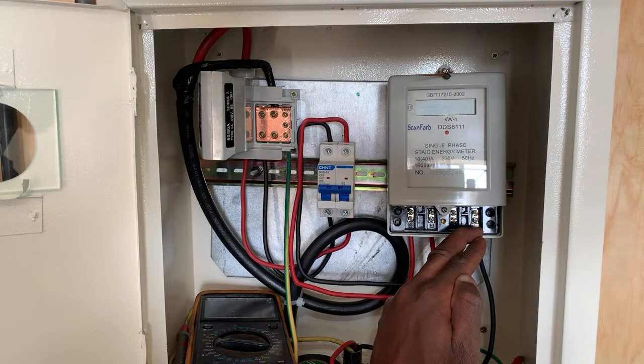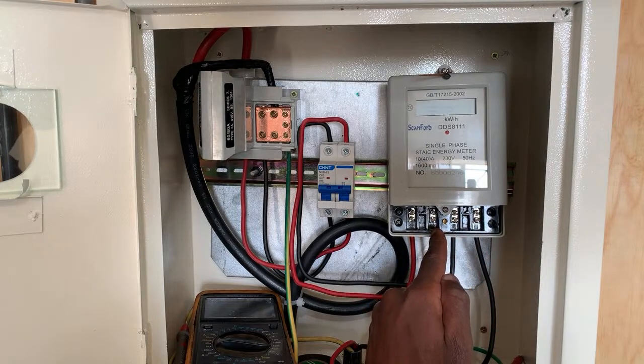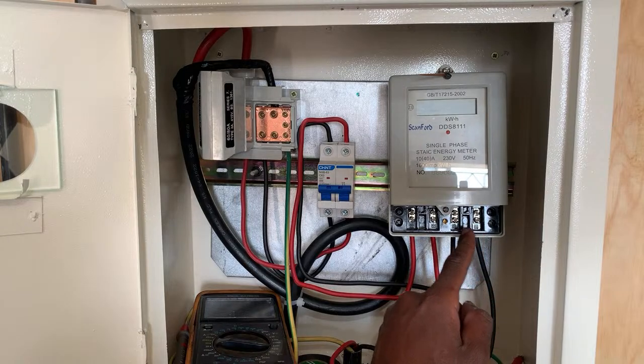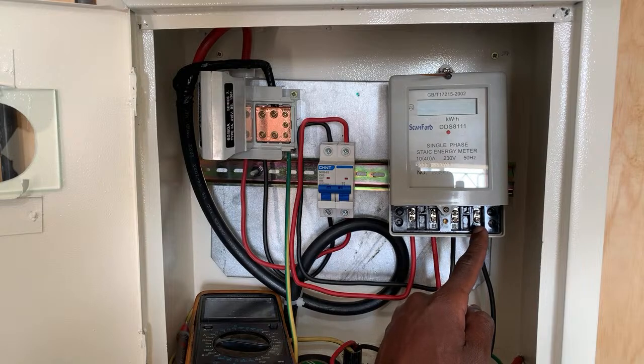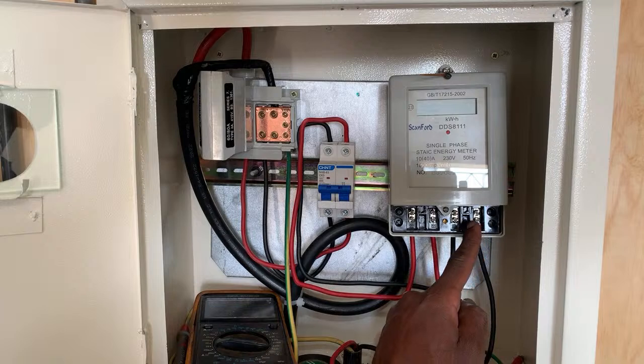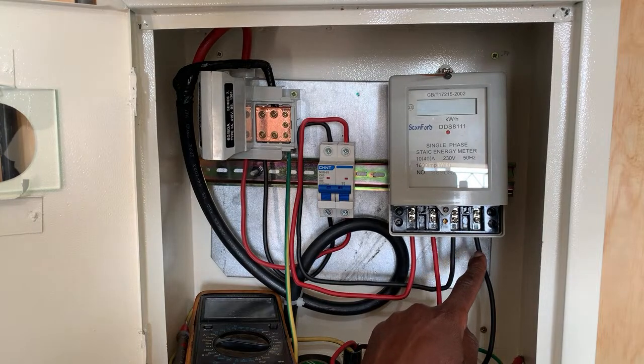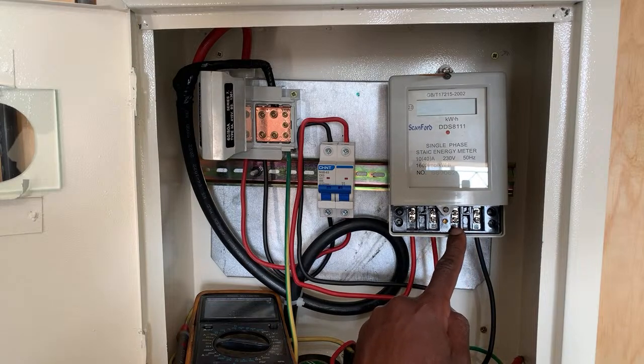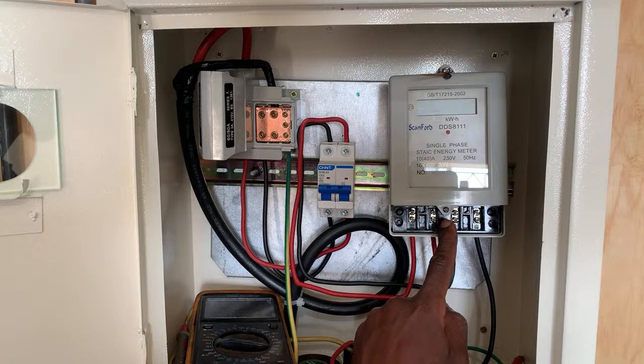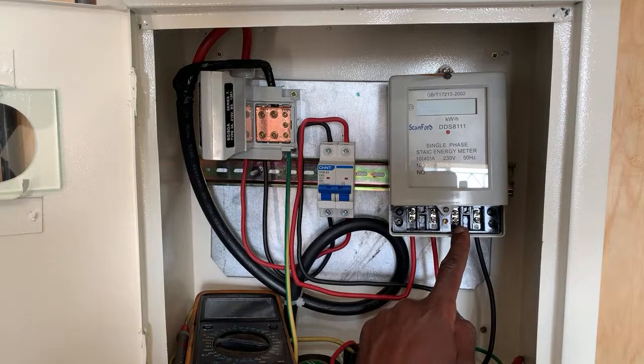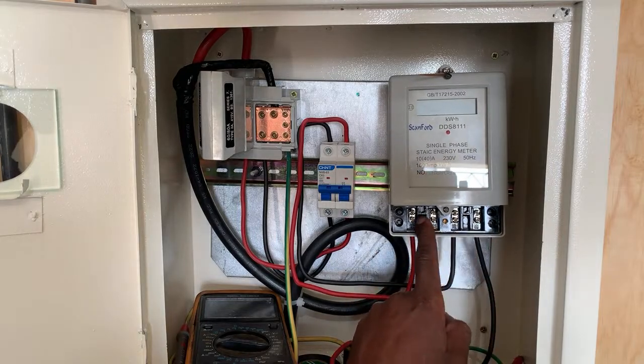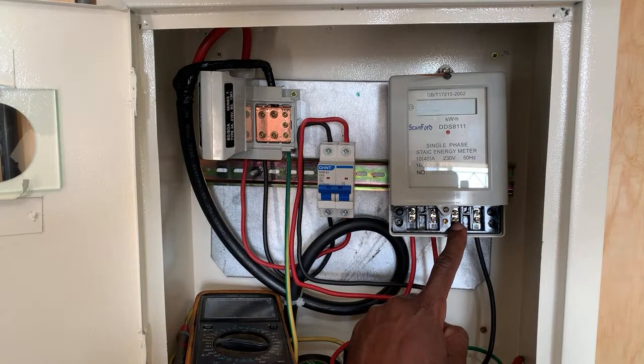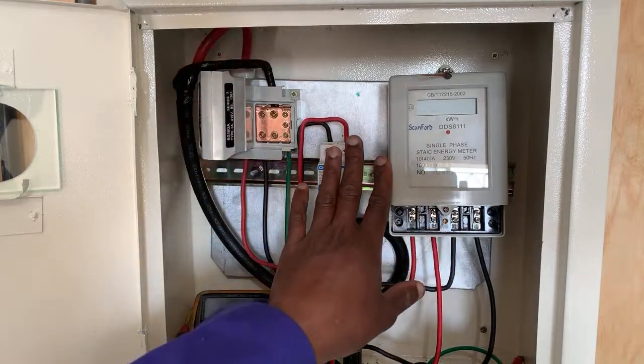And if there is a loose connection at the load section where the output of the phase and the neutral is compromised, then the cables will have been overheating and they have burnt the connections. The connections are hot most of the time. In most cases, this will happen if someone screwed on the insulation, or they did a bad job at tightening that connection. So with time, these connections have been burning, and once they burn, they affect how electricity is conducted to that house. So you'll find that the energy meter is on. Everything all the way here is okay.